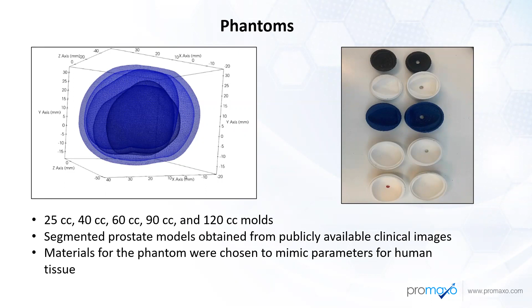This initial study to assess the navigation accuracy of the low-field Promaxo MRI system was performed on prostate phantoms. 5 phantom sizes were used to span a range of prostate volumes and different prostate shapes, as can be seen in the image on the left. Prostates from different patients were segmented to generate a 3D model, and molds in the second image were created from them. Materials for the phantom were experimentally determined to mimic parameters for human tissue.